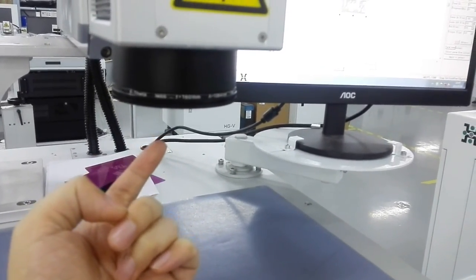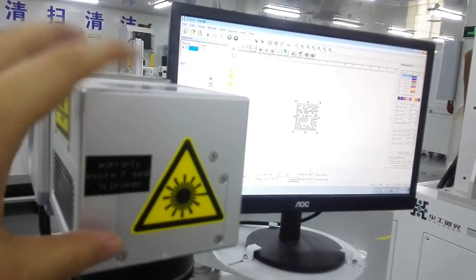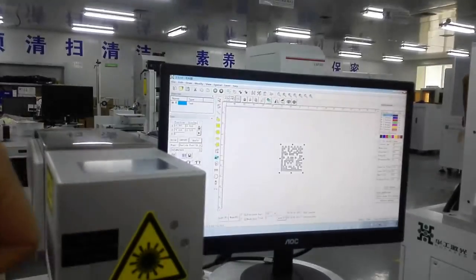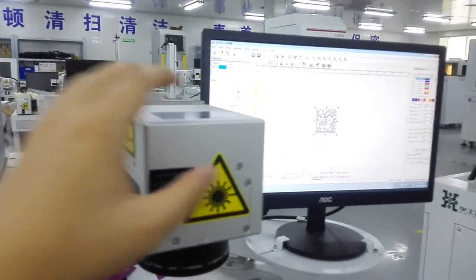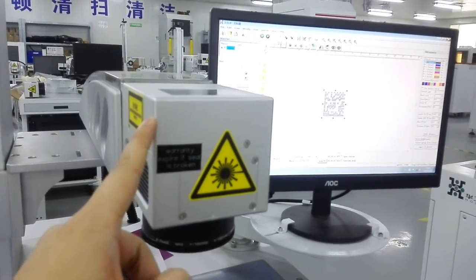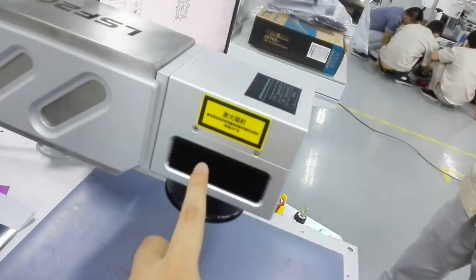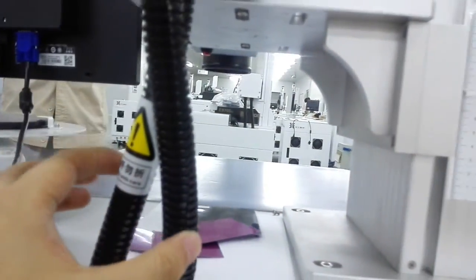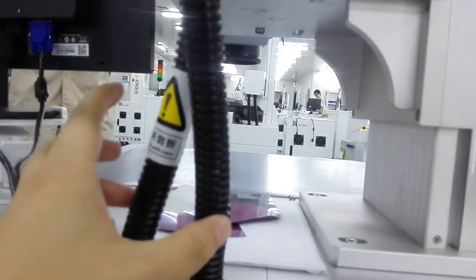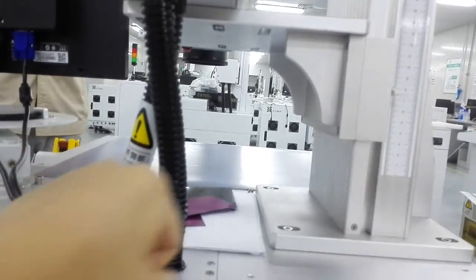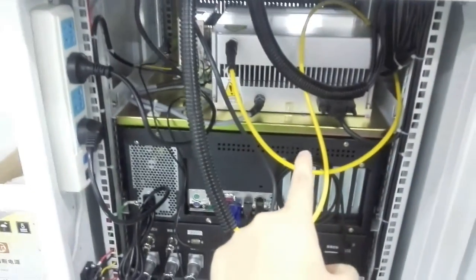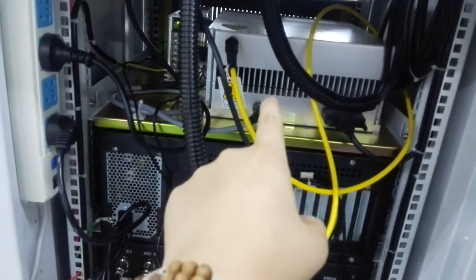Also, inside of the galvo head, there are two micro motors inside. Don't get it punched or get it seriously shaken. Otherwise, you'll get this galvo head damaged. You can see the laser is coming out from this galvo head, but transmitted by this fiber cable. It's very easily broken. It's fragile. Don't punch it. Keep it with some certain distance. Inside the cavity, you can see the laser source. Don't get the yellow cable broken and make sure the laser source is in clean condition.